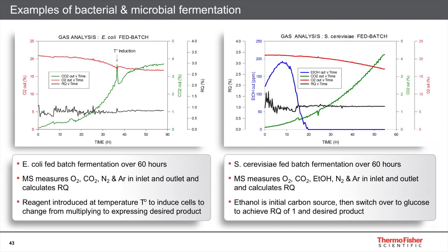Examples of bacterial fermentation processes monitored by mass spectrometry include two fed-batch fermentation processes. In the E. coli fed-batch process, lasting approximately 60 hours, the mass spectrometer monitors oxygen, CO2, nitrogen, and argon in the inlet and outlet, calculating respiratory quotients in real time. At the point when a reagent is introduced, cells change from multiplying to expressing the desired product — observed as the stabilization of the respiratory quotient at about 40 hours, settling to the expected value of 1.